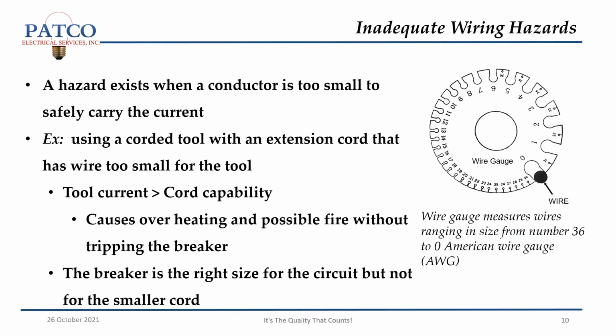Inadequate wiring hazards. A hazard exists when a conductor is too small to safely carry the current. For example, using a corded tool with an extension cord that has too small wire for the tool. Tool current greater than cord capacity. This causes overheating and possible fire without tripping the breaker. The breaker is the right size for the circuit, but not for the smaller cord.